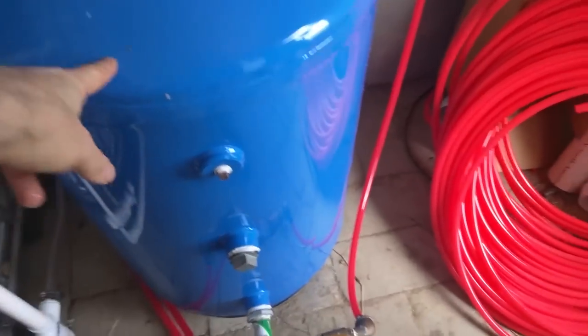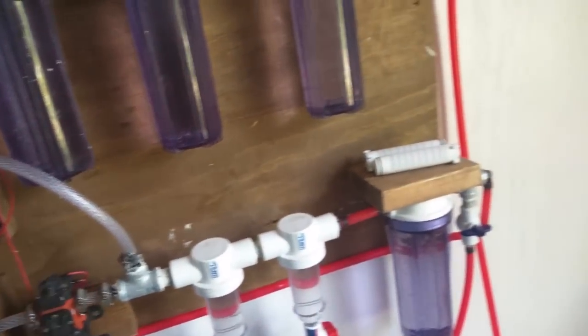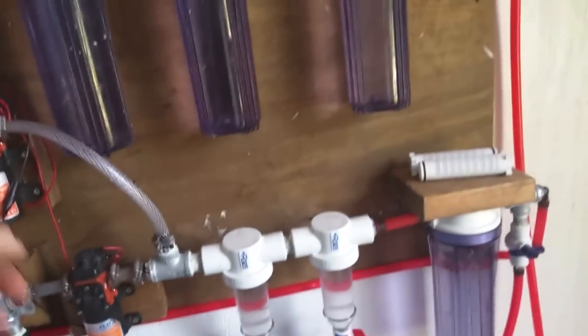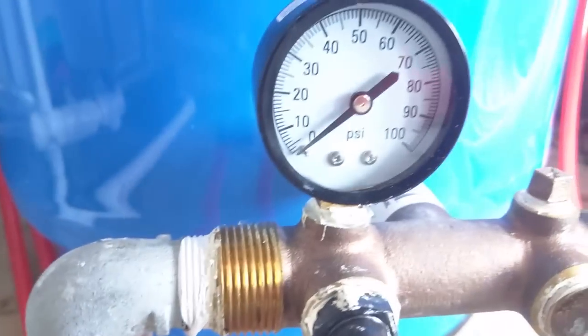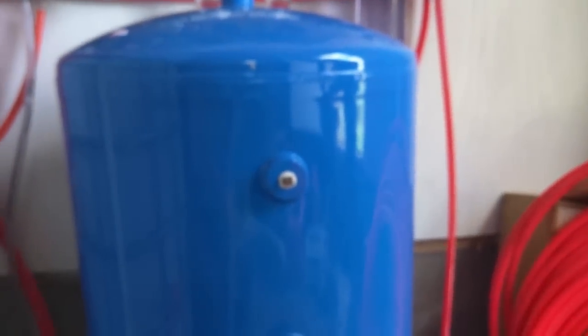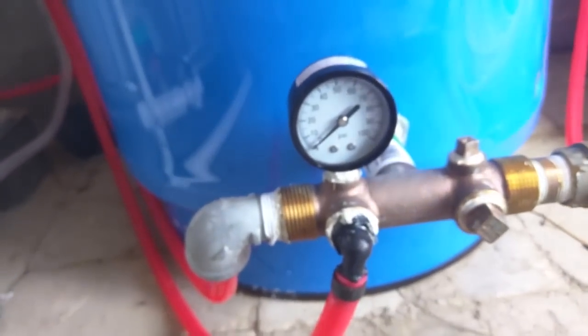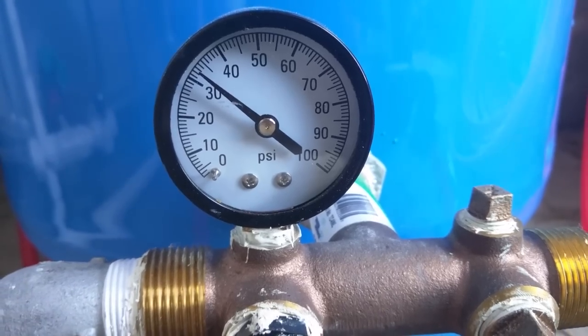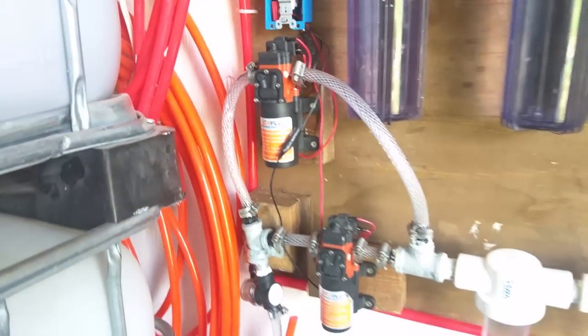Let's turn the pump back on. Right now the pressure tank is filling — the pumps are working. These are only 35 psi pumps; we'll see how it works after all the filters. We might have to replace them with higher-pressure pumps, but we definitely see pumping activity. The gauge should be going up. This is a 40-gallon tank, maybe two-thirds usable storage — about 30 gallons — so it should fill up in about 15 minutes at two gallons per minute. The pump shut off at 33 psi with no major spurts of water anywhere.